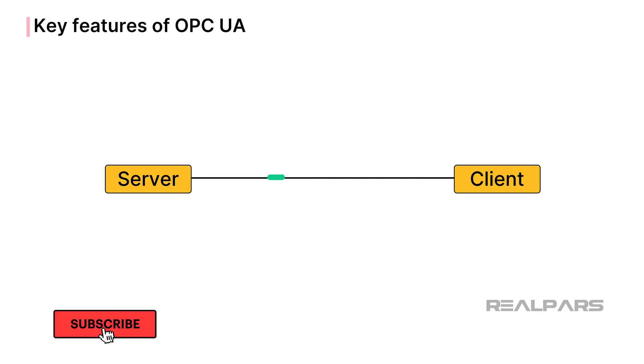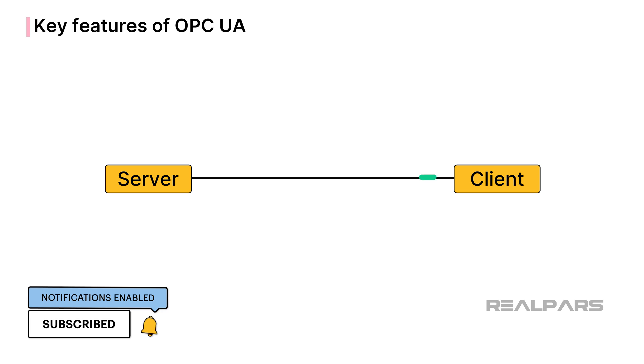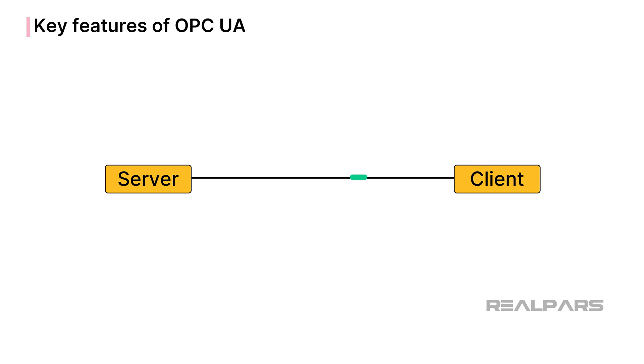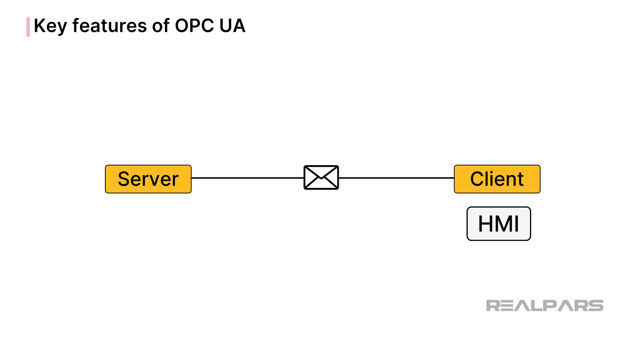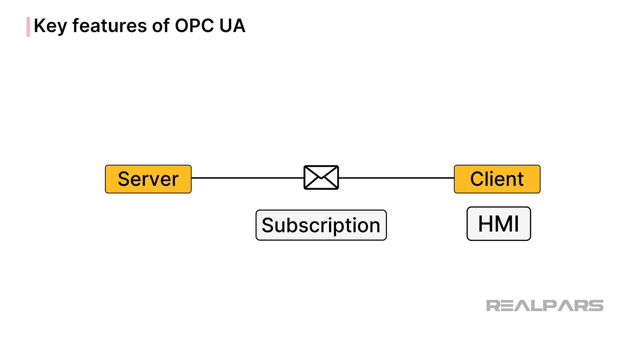OPC UA is a client-server based application. The OPC UA server provides access to its data by exposing its data objects to an OPC UA client, such as an HMI application. The OPC UA interface is defined through configuration. An OPC UA application on the client subscribes to the data objects in the OPC UA server. These subscriptions are comprised of one or more data links to objects in the server, that are used to request data from the server.